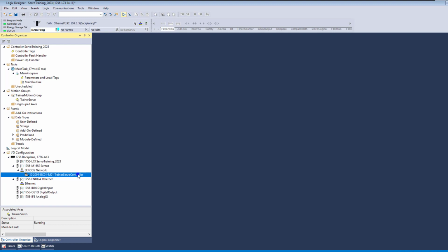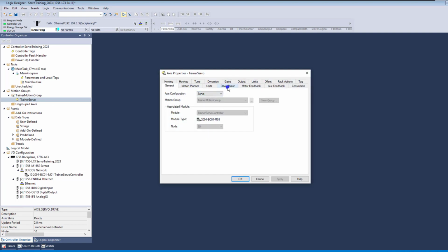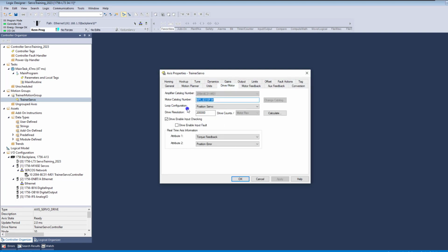That means basically 1 through 3, like I believe 2 is checking the module, checking the actual drive. 2 or 3 is checking that the drive and the servo are attached, and that the actual servo motor itself is installed properly, meaning if you go into properties, you did select the proper motor that is being used, meaning it does look at the encoder and make sure the encoder is what it's supposed to be.